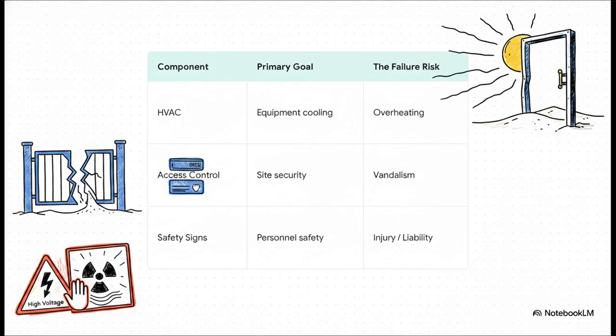Take access control. It's not just about swiping keycards, it's about the physical integrity of the room itself. In remote desert areas, extreme heat can actually warp heavy metal doors. If that seal breaks, sand and humidity just pour right in. And those safety signs? They aren't just legal decorations. When a sign warns of high voltage or dangerous RF microwave radiation, it's warning of actual physical effects, like serious RF burns. You have got to respect the stop zones.